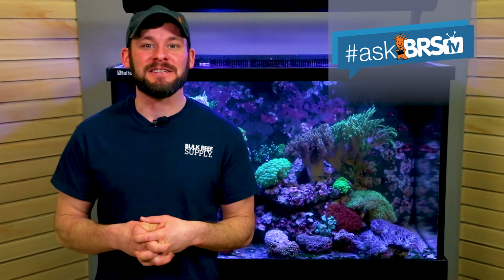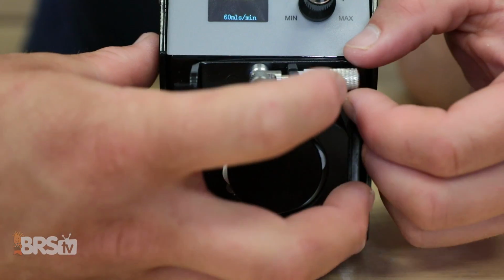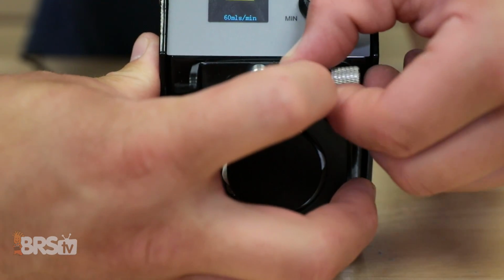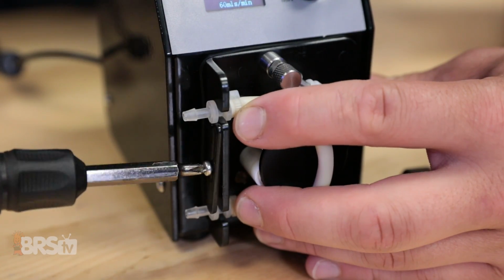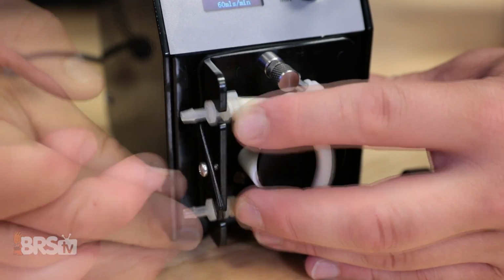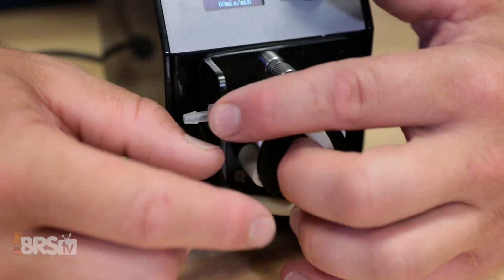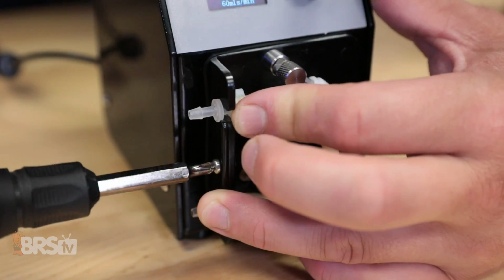Starting with the tubing replacement, all I need to do is loosen the tensioner that holds the tubing onto the pump head rollers and release it from the bracket. From there, I just need to loosen the bracket screw that holds the tips of the tubing on the pump, slide out the plastic tips, pop in my new replacement tubing, and tighten everything down again.